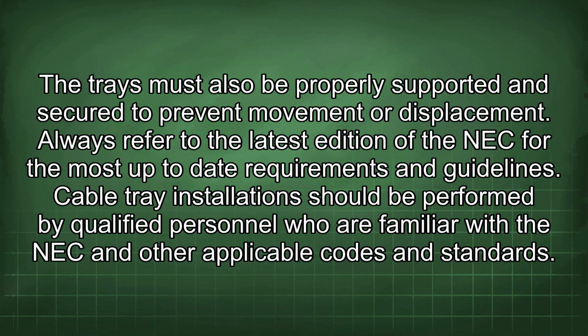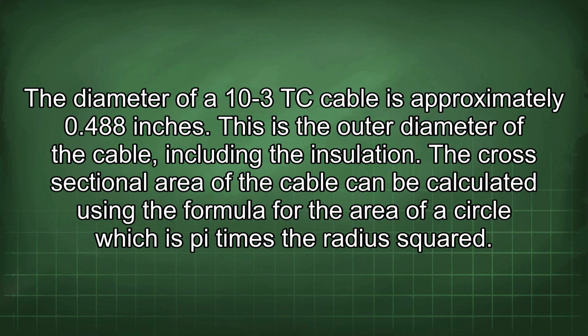Cable tray installation should be performed by qualified personnel who are familiar with the NEC and other applicable codes and standards. The diameter of a 10-3 TC cable is approximately 0.488 inches. This is the outer diameter of the cable, including the insulation. The cross-sectional area of the cable can be calculated using the formula for the area of a circle, which is pi times the radius squared.